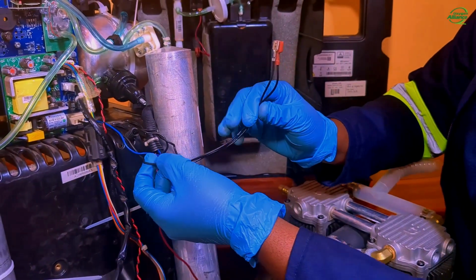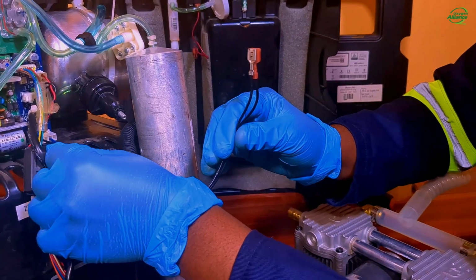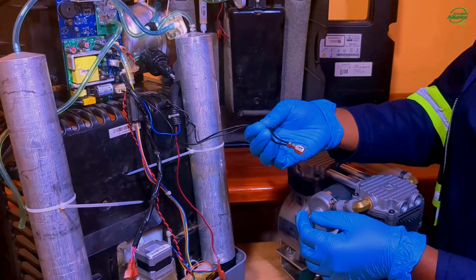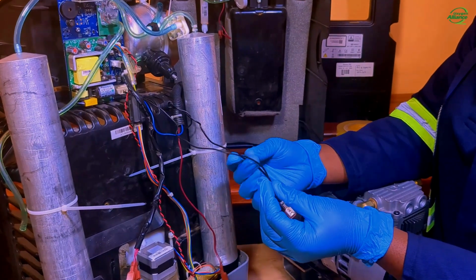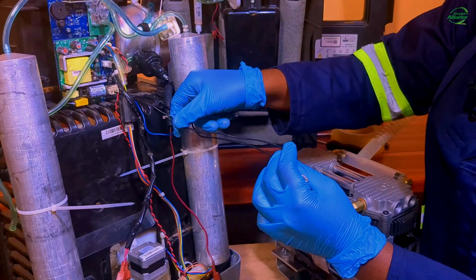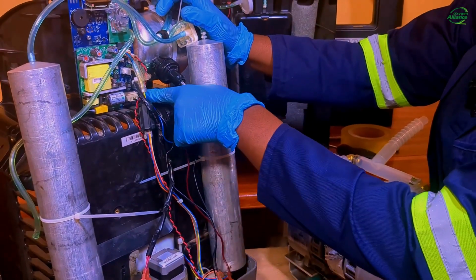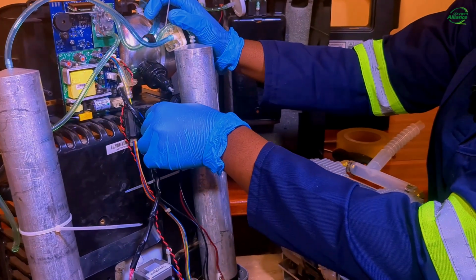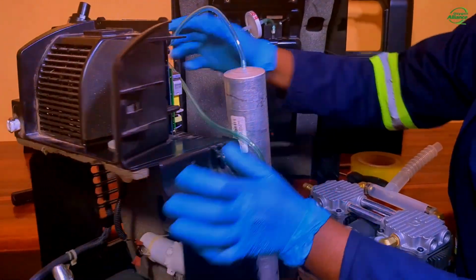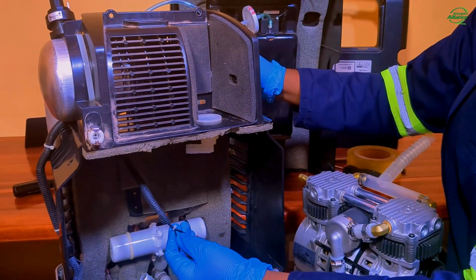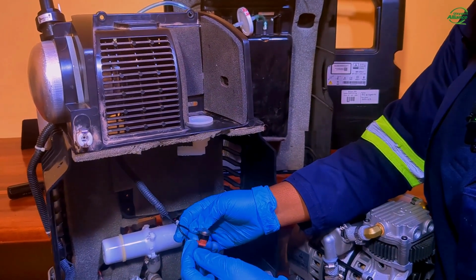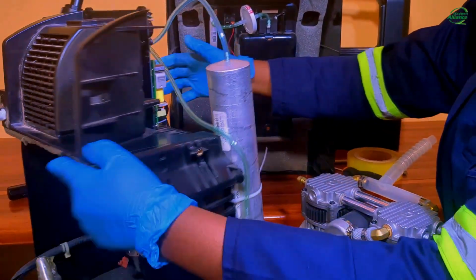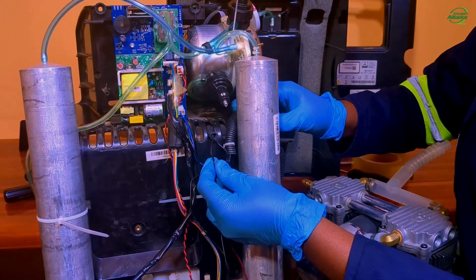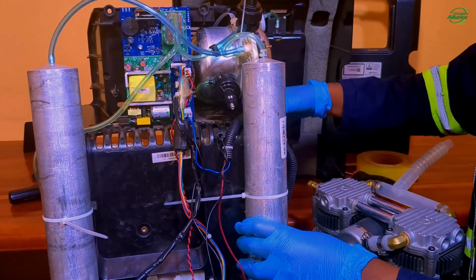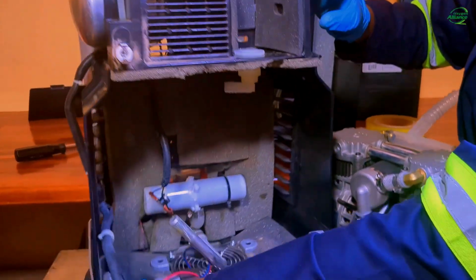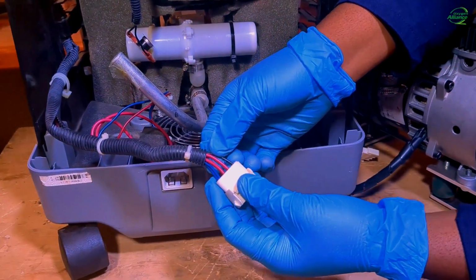So as you can see, this cable is going together with the neutral wire, which are supplying power to the board. So this one, as you can observe, has two wires, both being live. This wire is supplying power to the board, whereas this wire is going straight to the thermal switch. So as you can see, it goes straight to the thermal switch, and one wire goes back and comes out here, and this is the live wire that sends power to the compressor. So you can see that the live wire is coming out here, which is going to supply power to the compressor.